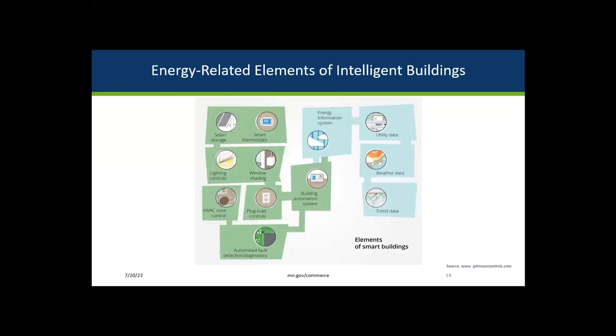This figure shows the intelligent building system related to energy use of the building. In the center of the graphic, the Building Automation System, or BAS, and the Energy Management Information System, or EMIS, serve as the brains of the intelligent building with a two-way feed of information and data. The BAS and EMIS control the building systems on the left, which include heating, lighting, ventilation, air conditioning, daylighting, plug loads, and distributed energy resources such as solar and energy storage.